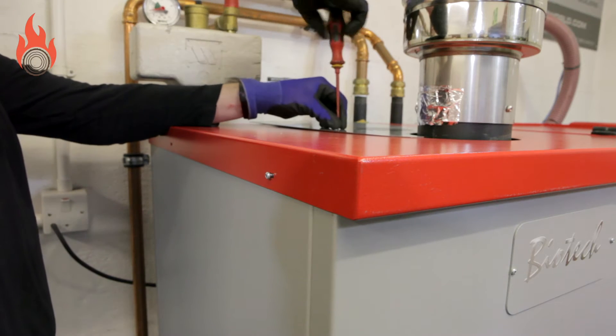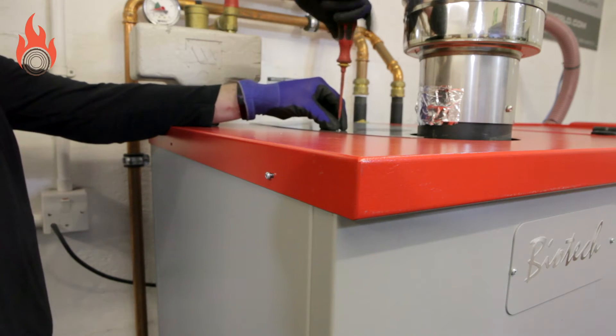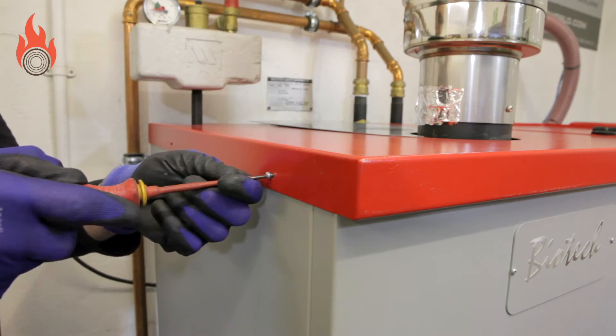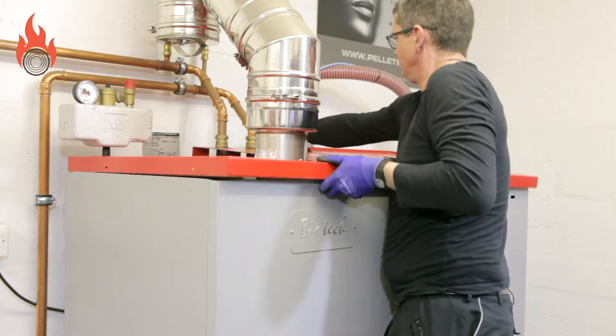To start the process of cleaning the heat exchanger tubes, remove the top cover. It is good practice to start cleaning a boiler from top to bottom, as any ash will fall down during the process and will be caught during the subsequent cleaning routines.